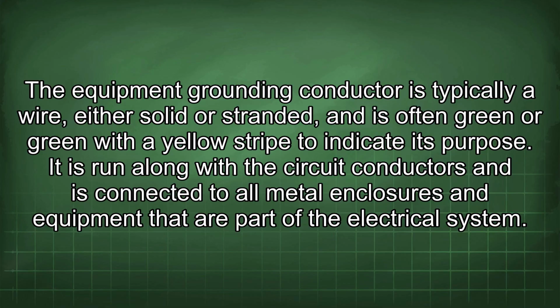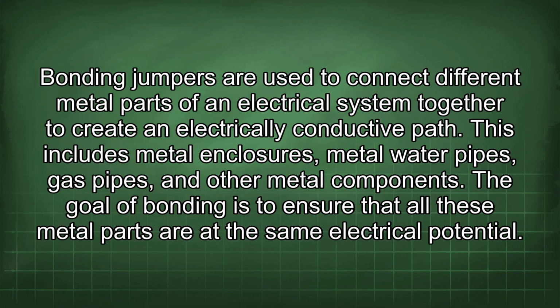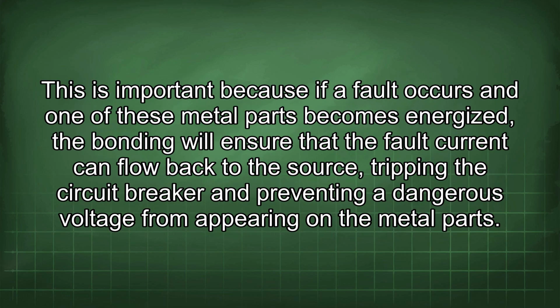It is run along with the circuit conductors and is connected to all metal enclosures and equipment that are part of the electrical system. Bonding jumpers are used to connect different metal parts of an electrical system together to create an electrically conductive path. This includes metal enclosures, metal water pipes, gas pipes, and other metal components. The goal of bonding is to ensure that all these metal parts are at the same electrical potential. This is important because if a fault occurs and one of these metal parts becomes energized, the bonding will ensure that the fault current can flow back to the source, tripping the circuit breaker and preventing a dangerous voltage from appearing on the metal parts.